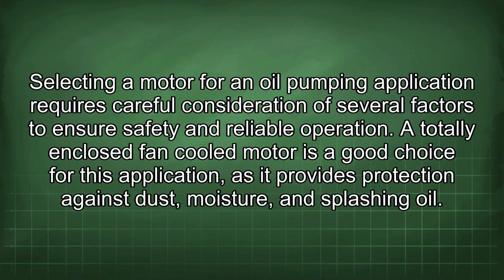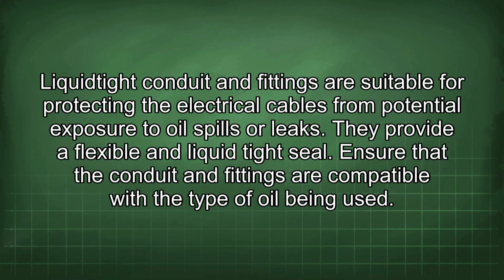Selecting a motor for an oil pumping application requires careful consideration of several factors to ensure safety and reliable operation. A totally enclosed fan-cooled motor is a good choice for this application, as it provides protection against dust, moisture, and splashing oil. Liquid-tight conduit and fittings are suitable for protecting the electrical cables from potential exposure to oil spills or leaks. They provide a flexible and liquid-tight seal.